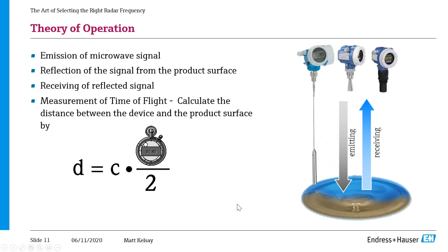So I'll cover just a little bit of theory. I don't want to spend too much time on this, but I do think it's important to just make sure everybody's got a base understanding of how they work. So both radar and ultrasonic measurement is based off of what we call the time of flight principle. A signal is emitted from the device, travels down to the product surface, where it's then reflected back up. What we're measuring is actually the time that it takes that signal to go down and back, which is proportional to the level in the tank or whatever you're measuring.